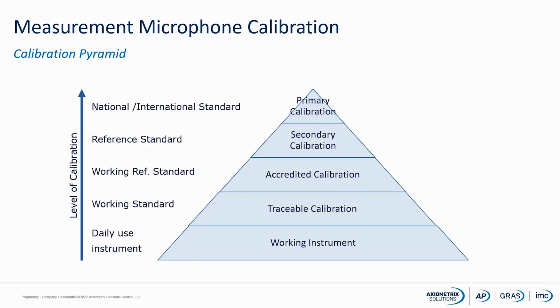Then you can select a traceable calibration, so it is traceable back to a national or international institute or standard. You can also have a level higher with an accredited calibration. An accredited calibration is a calibration performed according to a certain standard, normally the ISO 17025 standard. You could also refer to a reference standard, so it's more a secondary calibration. It's still an accredited calibration, but there's more accuracy in what has been done.